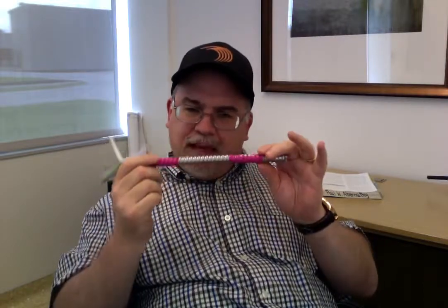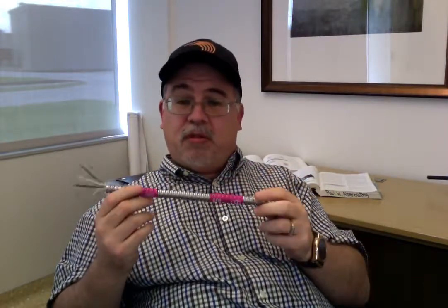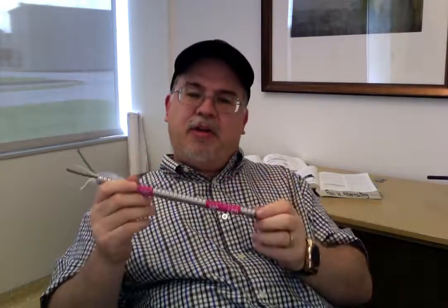Once they get into that product, then they will meet their required separation. That's an installation practice, and it's going to work in coordination with the manufacturers of that equipment, where they put the terminations in order to have that separation take place. But as far as the assembly, I can run them together in this, and it's not a violation of anything within the National Electrical Code, and now UL 1569 has no problem with it at all. So that's the application for that product. Save you a lot of time and labor. You don't have to run separate Class 2, Class 3 for your lighting applications for dimmers or power management systems for lighting. You can do it with one cable. So that's an advantage there.